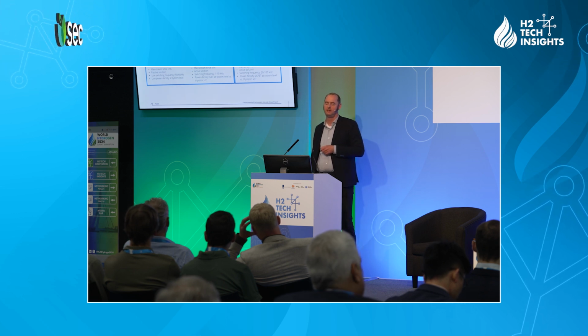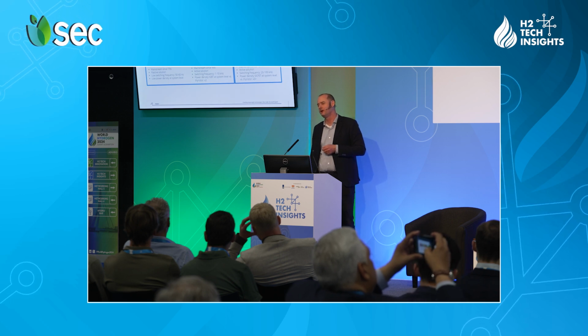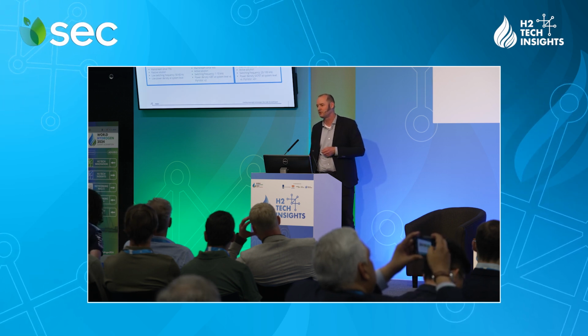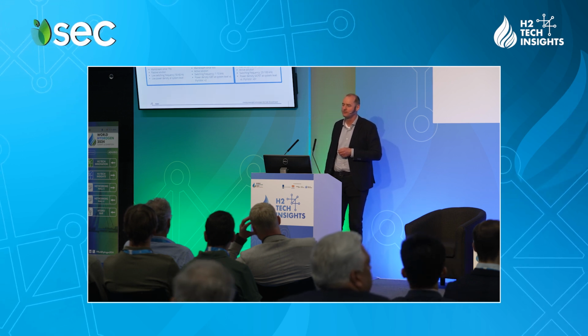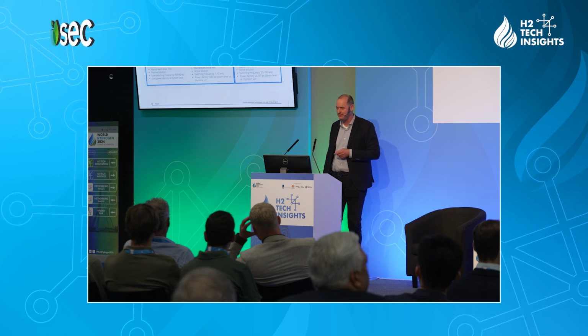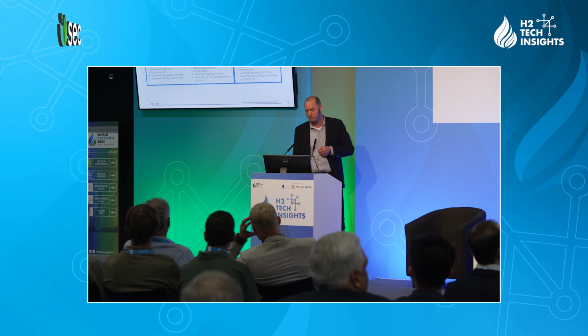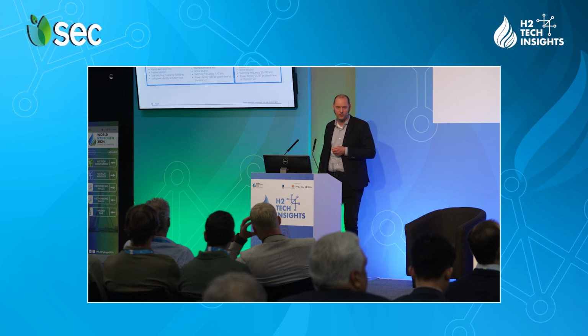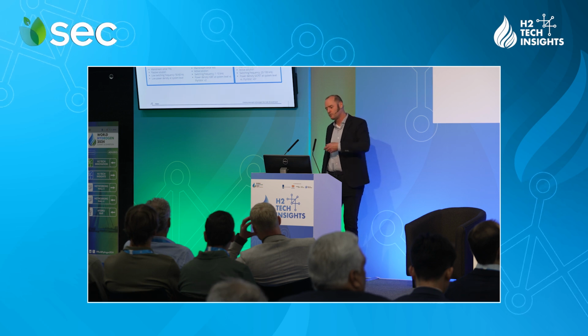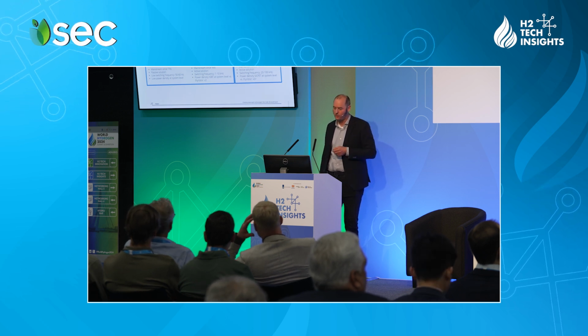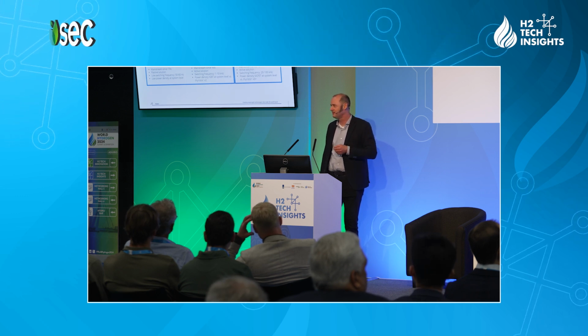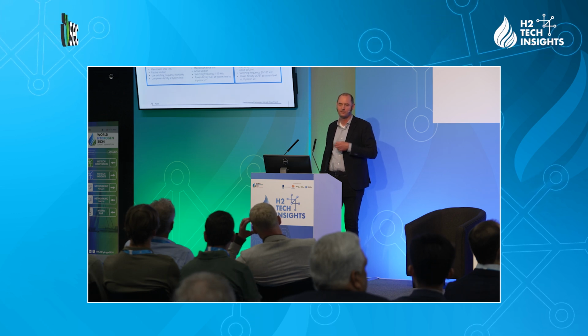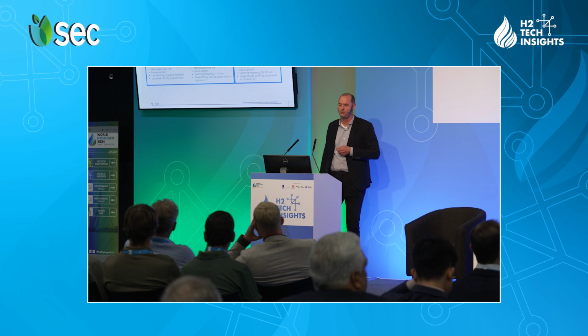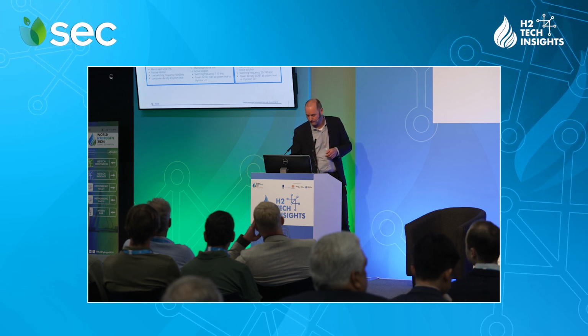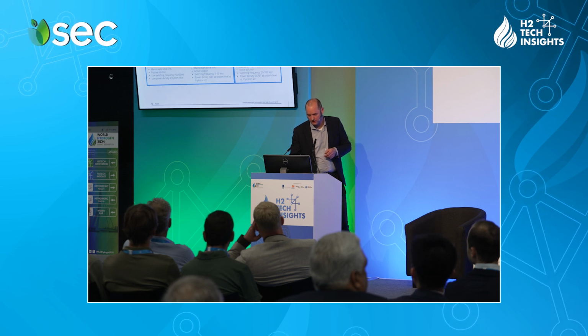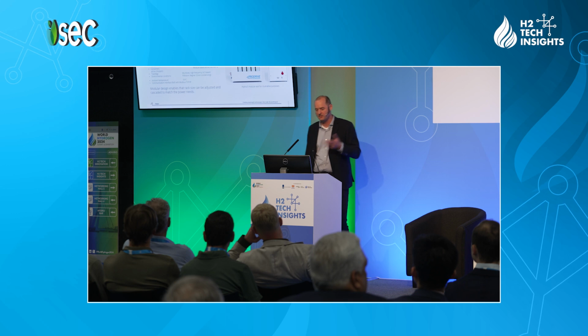But in the last 5-6 years, and actually we've been using this since 2011, silicon carbide has become quite commonly used technology. All electric vehicles, for example, are almost 100% based on silicon carbide technology nowadays. So in terms of reliability, very big steps have been made. It is again an active solution, and the switching frequency is again much higher than what IGBTs are offering. So this technology is much more agile in dealing with whatever the grid is throwing at you. And the power density is, if I look at the systems out there, easily a factor of 3, but I've also seen a factor of 5, smaller than the total system based on thyristor-based systems.